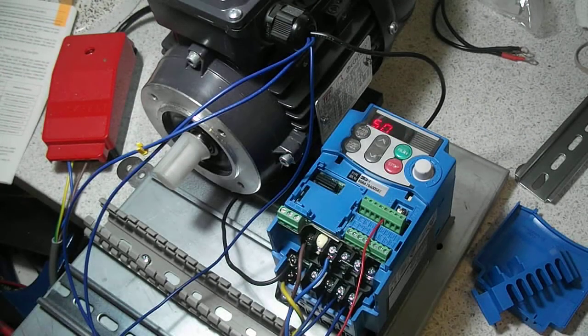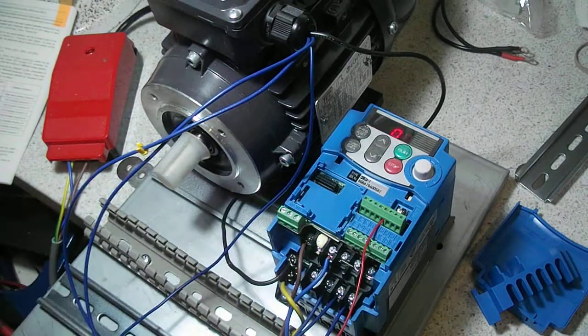So all I want at the moment is just another frequency. I want to get it down to half speed, so I'm going to set function C05 to 25 Hertz. So the way you do that, let's zoom in again so you can see what I'm doing.